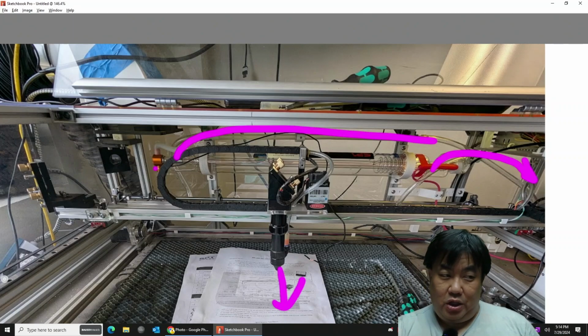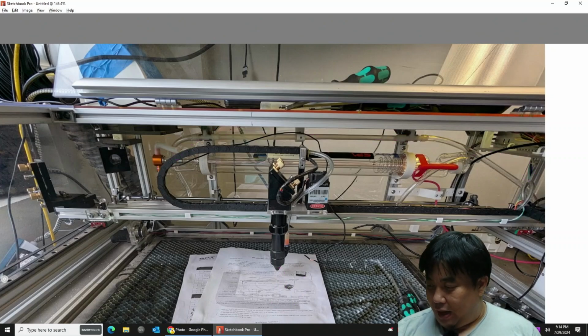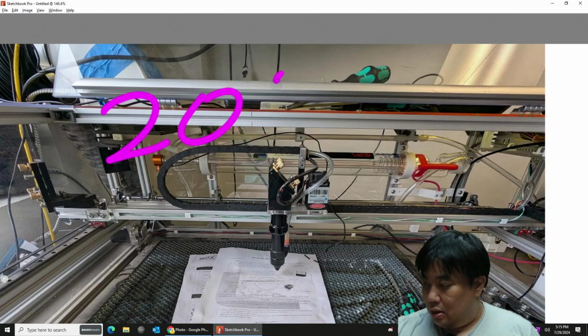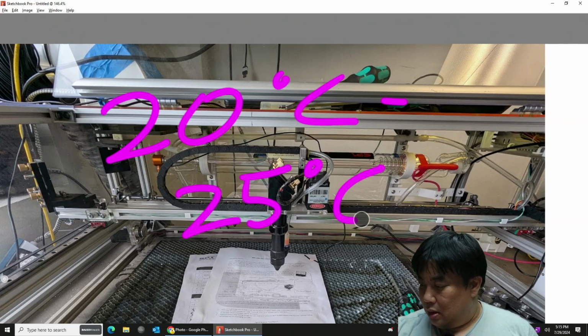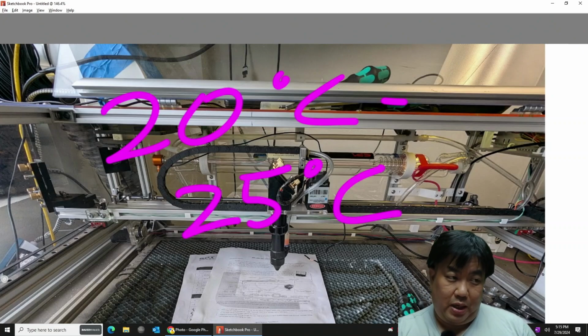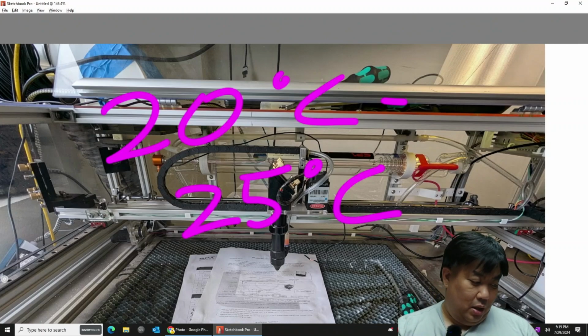If you look at the spec sheet, numbers get even worse from there. The spec sheet calls for about 20 to 25 degrees centigrade water temperature. But on a hot day here in Everett, we can be walking in and that tube is already at 27 degrees. So there's really zero headroom. So what are we doing different?